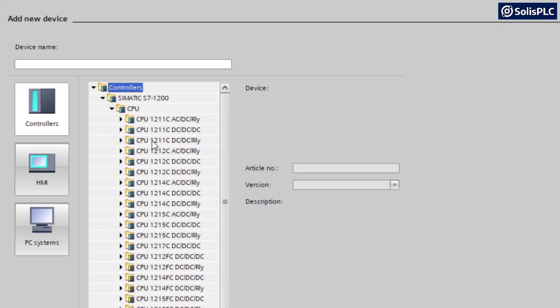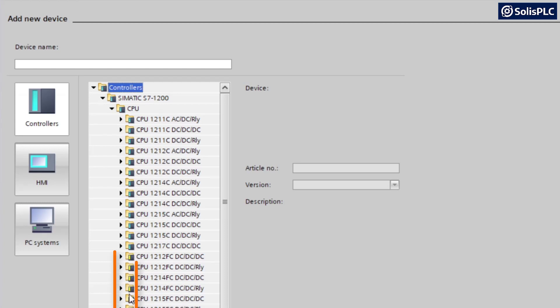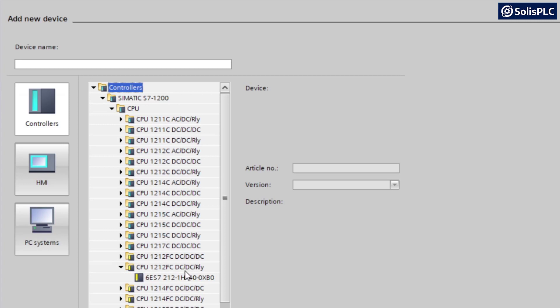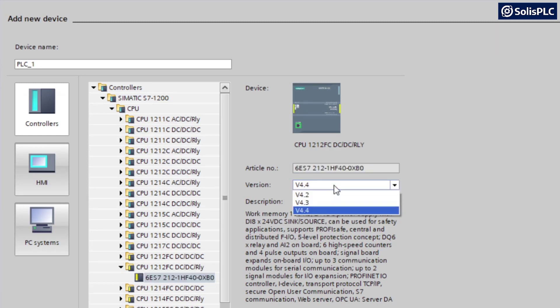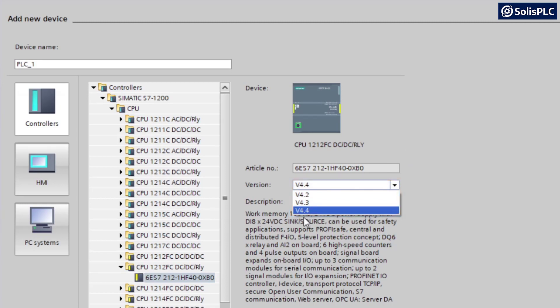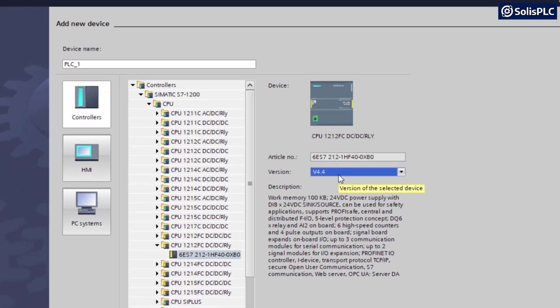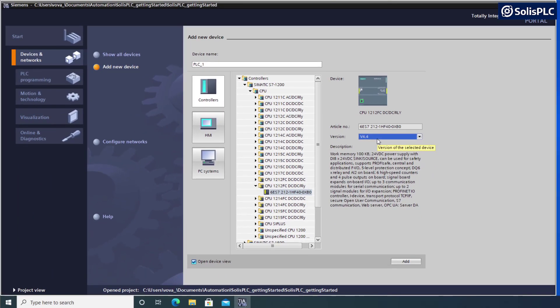If you want to simulate a PLC, you can certainly select any device that is covered under your specific license. I have a safety PLC, which in the Siemens world is going to be labeled with a yellow bar here that you can see on the bottom of all these CPUs. You do need to find the right model based on your hardware. For my specific case, that's going to be the 1212 FC DC-DC relay PLC. When selected, it's going to show the part number and the firmware. By default, it's going to select the highest level of firmware based on what's installed in TIA Portal. We're going to press on Add, and that should add a PLC to our project.